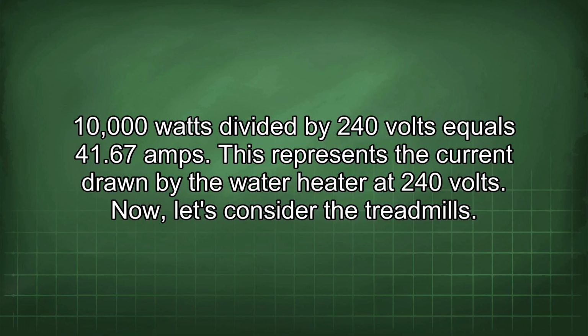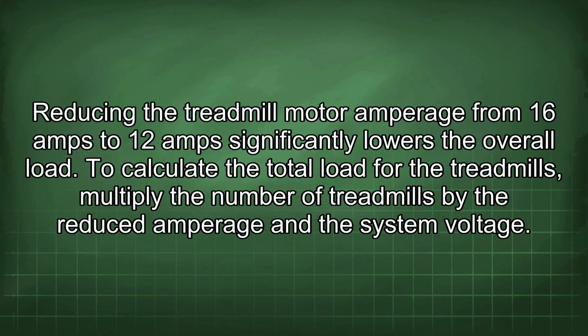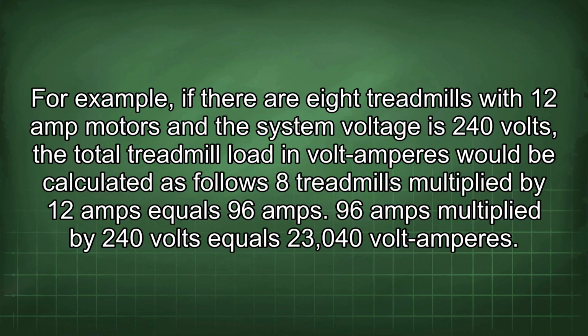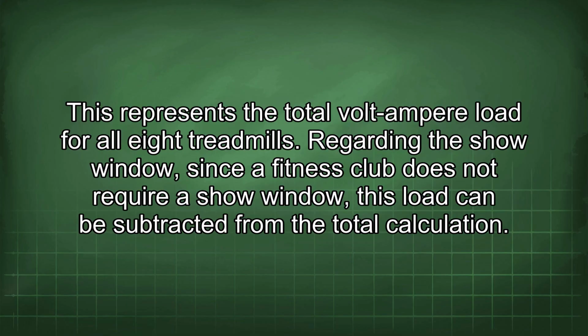Now let's consider the treadmills. Reducing the treadmill motor amperage from 16 amps to 12 amps significantly lowers the overall load. To calculate the total load for the treadmills, multiply the number of treadmills by the reduced amperage and the system voltage. For example, if there are 8 treadmills with 12 amp motors and the system voltage is 240 volts, the total treadmill load in volt-amperes would be calculated as follows: 8 treadmills multiplied by 12 amps equals 96 amps. 96 amps multiplied by 240 volts equals 23,040 volt amperes. This represents the total volt-ampere load for all 8 treadmills.